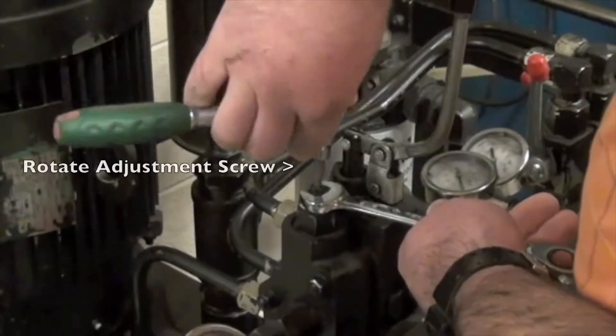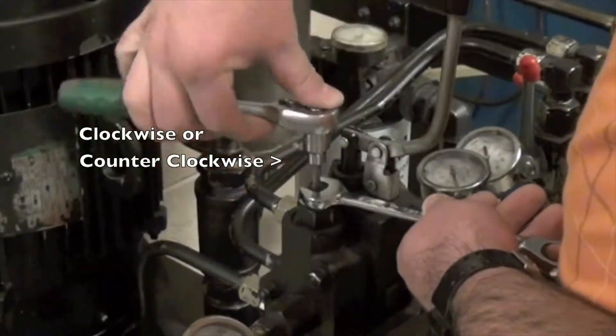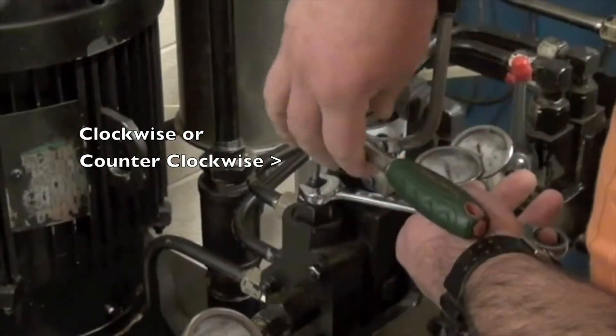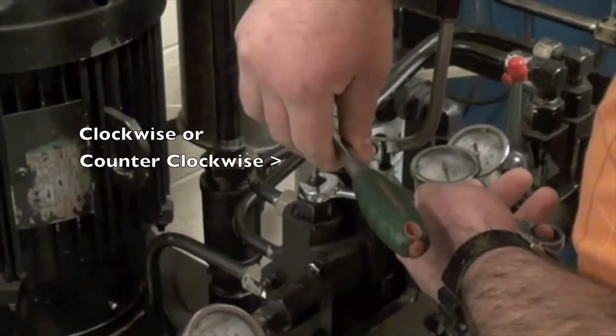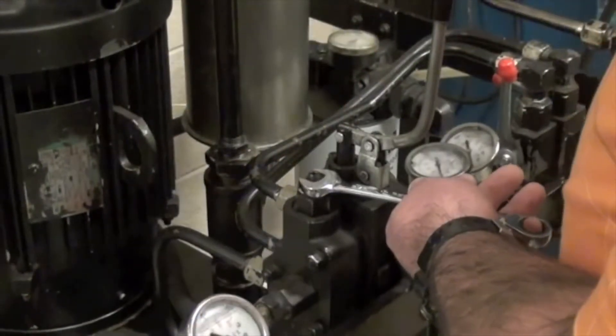Step 3. Rotate the adjustment screw clockwise to increase the relief pressure or counterclockwise to decrease it. As a rule of thumb, a quarter turn can have dramatic effects on the pressure. Sometimes a slight turn is all that's required.